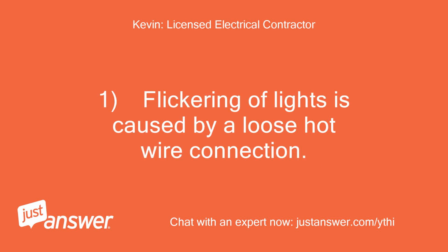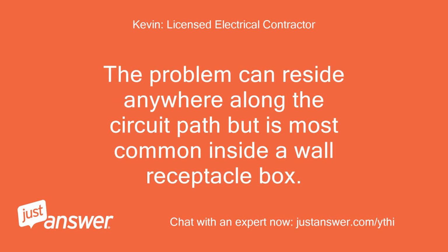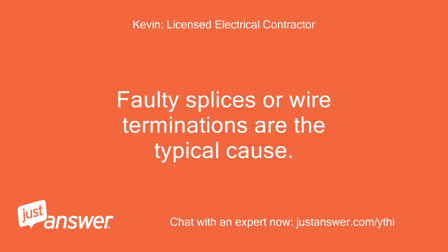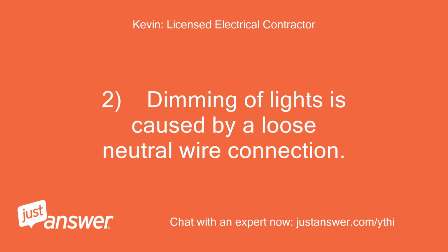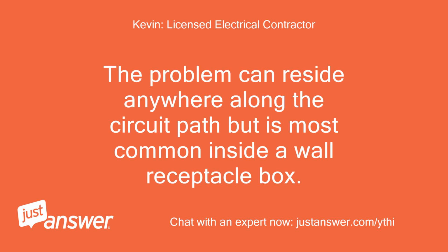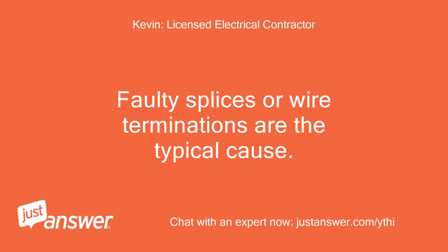1. Flickering of lights is caused by a loose hot wire connection. The problem can reside anywhere along the circuit path but is most common inside a wall receptacle box. Faulty splices or wire terminations are the typical cause. 2. Dimming of lights is caused by a loose neutral wire connection. The problem can reside anywhere along the circuit path but is most common inside a wall receptacle box. Faulty splices or wire terminations are the typical cause.